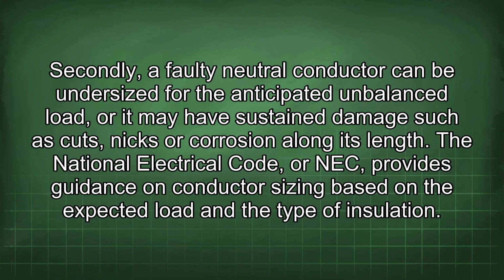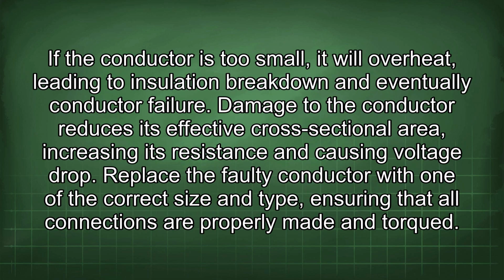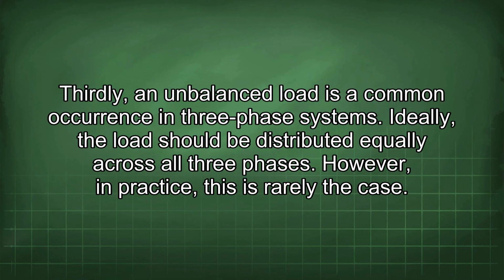The National Electrical Code, or NEC, provides guidance on conductor sizing based on the expected load and the type of insulation. If the conductor is too small, it will overheat, leading to insulation breakdown and eventually conductor failure. Damage to the conductor reduces its effective cross-sectional area, increasing its resistance and causing voltage drop. Replace the faulty conductor with one of the correct size and type, ensuring that all connections are properly made and torqued. Thirdly, an unbalanced load is a common occurrence in three-phase systems.